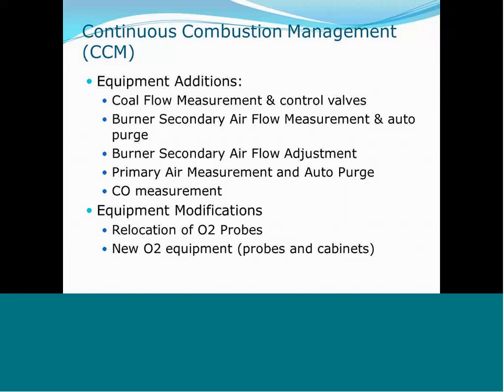And they had an existing primary air system, which they kept. They just put an automatic purge system on it to make sure the integrity of it would be maintained. They had O2 probes. They moved them to an area they felt is more representative of good excess O2 as caused by the burners. And they also added CO measurement very close to the O2 probe so that they had an idea of what the CO was across the back end.